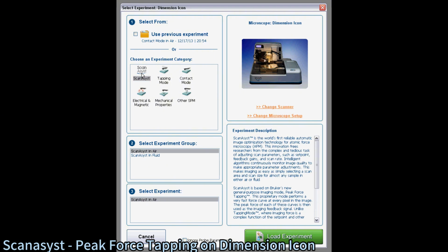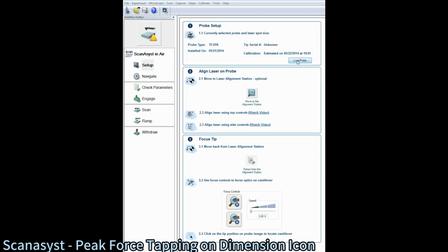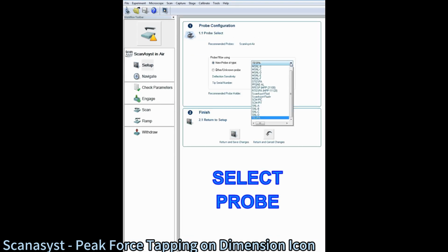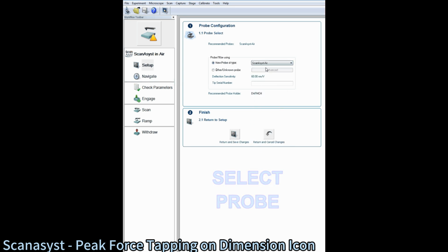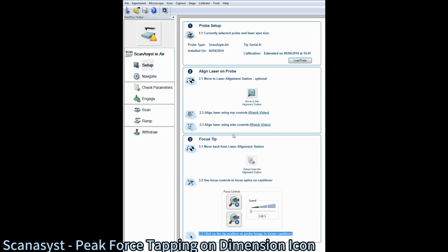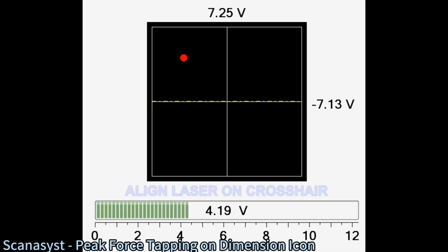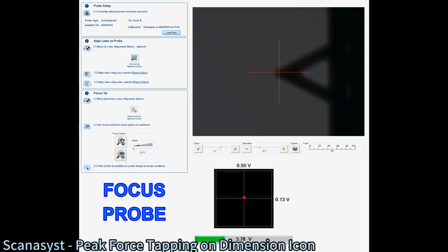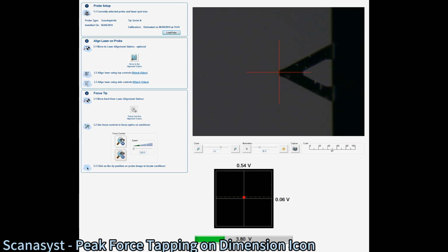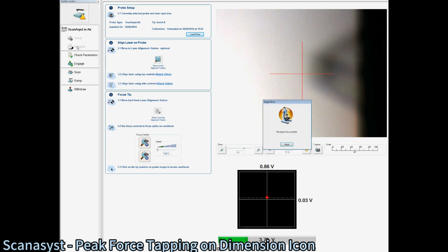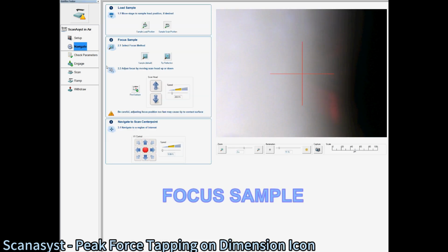Select ScanAsyst from the menu of experiment categories. Select the experiment group and then click the Load Experiment button. The software configures the system and opens the workflow toolbar. From the Setup interface, click on the Select Probe button to access the pull-down menu of probes. Select the ScanAsyst probe and then save the change. From the Setup interface, perform the final alignment of the laser into the detector. Select the Navigate icon to open the head and stage positioning controls. Use the Z motor position controls to raise or lower the head if necessary to obtain a focused image of the sample.